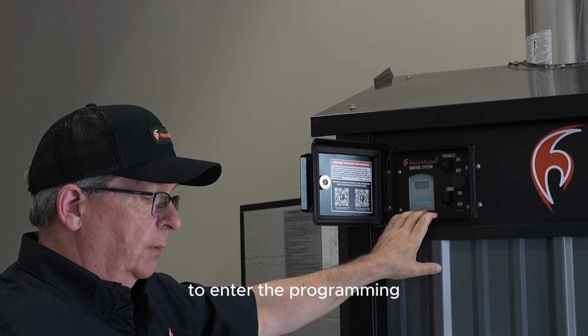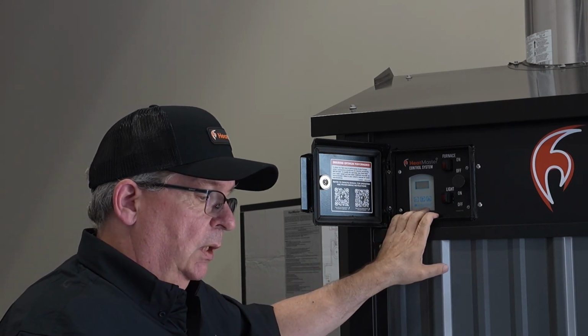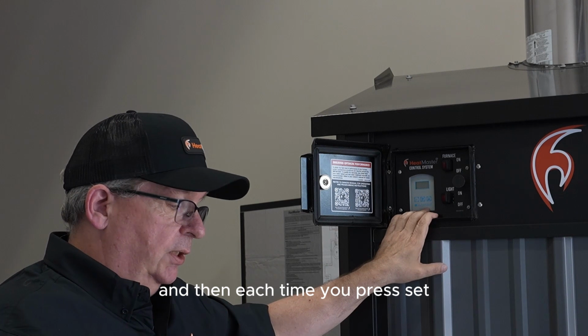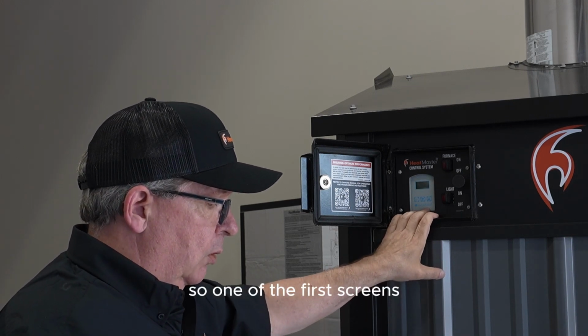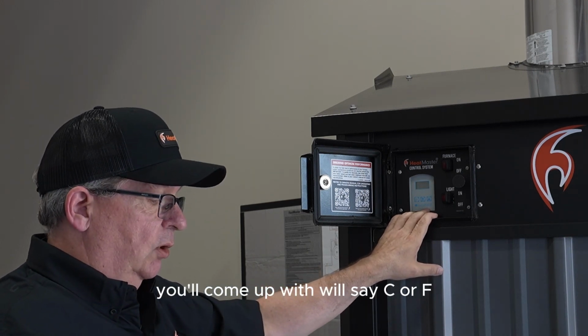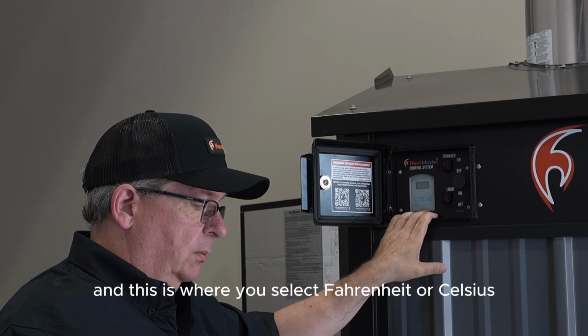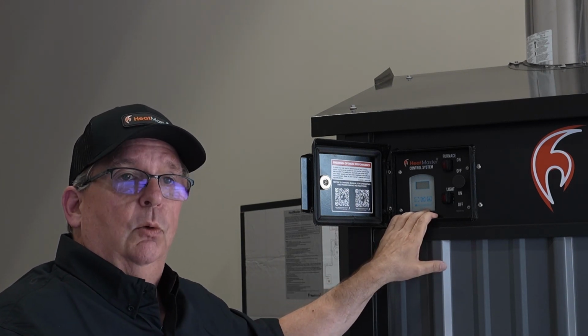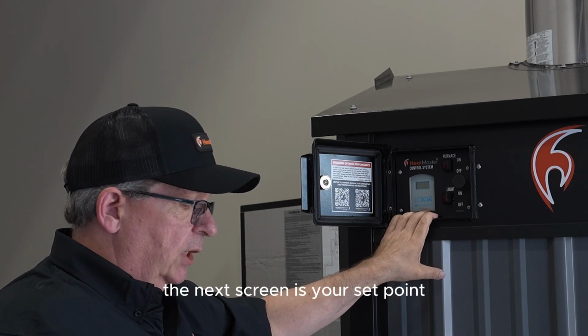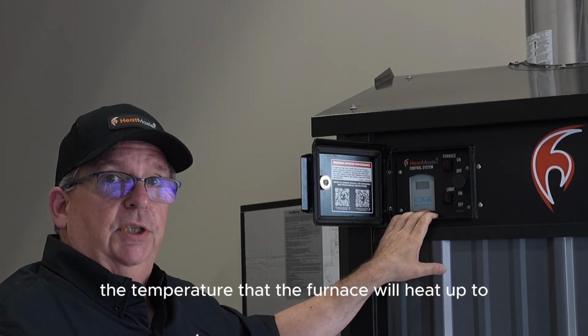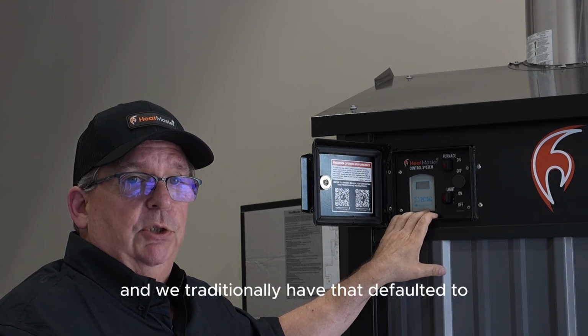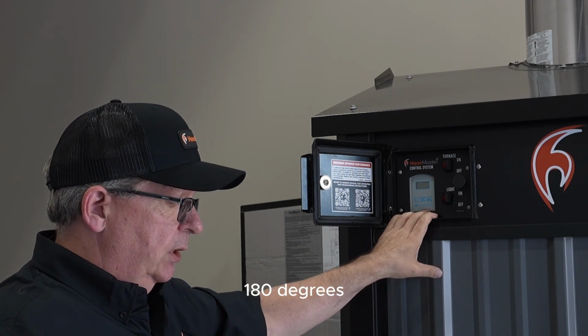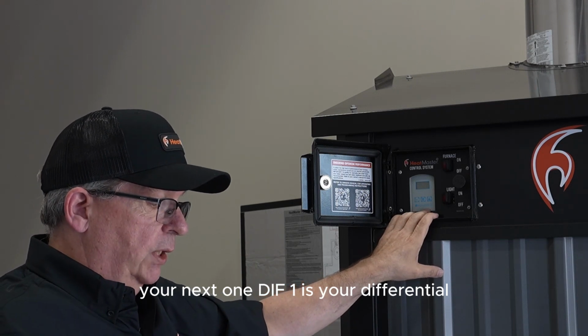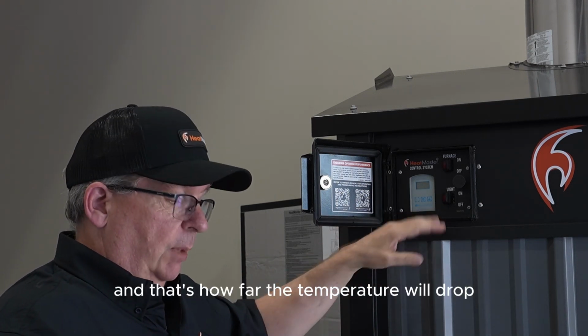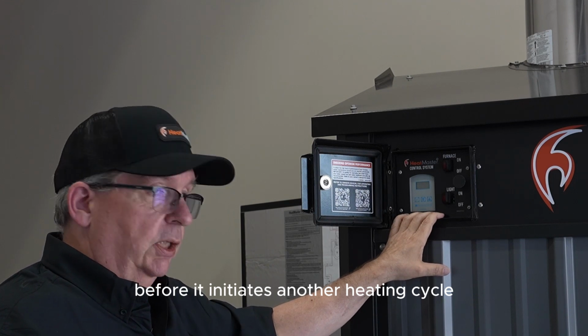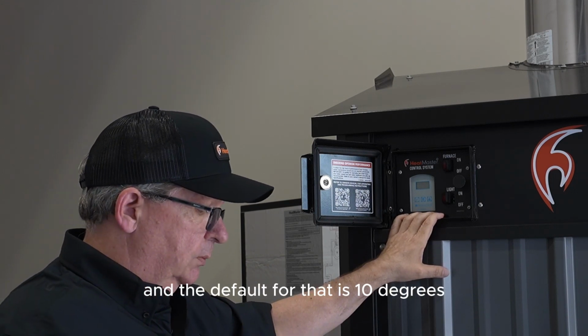To enter the programming, you're going to first press the set button. And then each time you press set, it will advance to another screen. So one of the first screens you'll come up with will say C or F. And this is where you select Fahrenheit or Celsius. We default to Fahrenheit. The next screen is your set point. So this is the temperature that the furnace will heat up to, and we traditionally have that defaulted to 180 degrees. Your next one, DIF1, is your differential, and that's how far the temperature will drop before it initiates another heating cycle, and the default for that is 10 degrees.